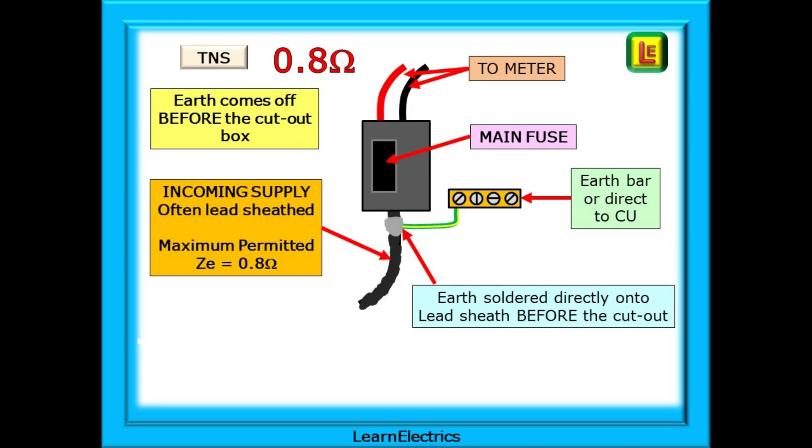Now look at this drawing of a TNS system. The big clue here is the great blob of solder just below the cutout box. It is from here, before the cutout, that we take the earth cable into the installation. Remember this layout. The earth may go to an earth terminal near to the cutout or it may go directly into the consumer unit. They are all slightly different so look for the solder blob. That is the giveaway. And ZE for a TNS system is 0.8 ohms maximum. Again, this is the ZE of the outside world and because it is older technology we have a higher maximum permitted ZE 0.8 ohms for TNS systems.